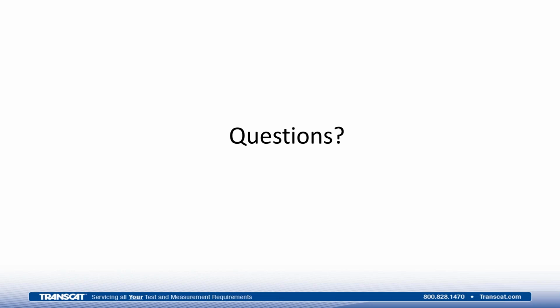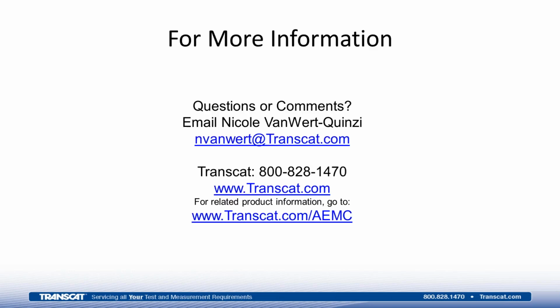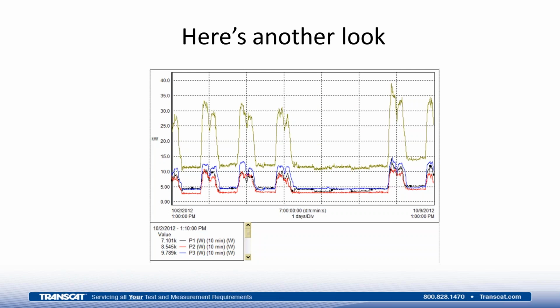First one, what is a load profile? What does it look like and what does it tell you? How do you use it? Okay, good question. The last graph I showed you is actually a load profile. This is a profile of a given load over time. What we could determine from it is the variation in the load relative to the time of day. This graph is not zoomed in, but if I was going to do an actual load profile on this particular motor or building, I would probably zoom into 1-day periods, so that the left-hand side was the beginning of a day and the right-hand side was 24 hours later. And I would look at that profile over time.